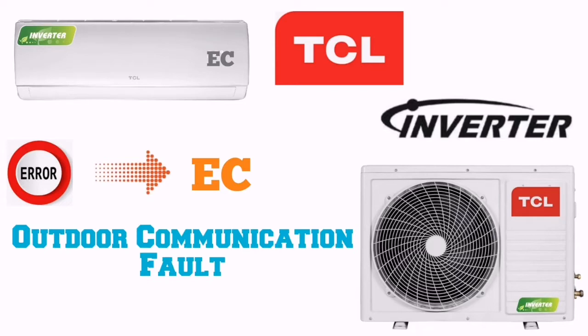And the second step, after the complete unit is energized, check the indicators on the outdoor power source board and the intelligent power module. The indicator on the power source board blinks normally, bright for 1 second and dark for 1 second, but the indicator on the intelligent power module does not work normally. Replace the intelligent power module. If the fault remains unsolved, replace the power source board again.